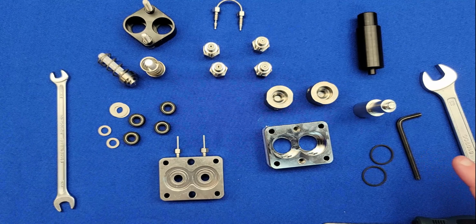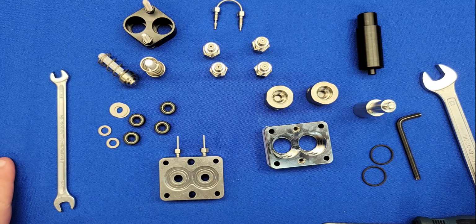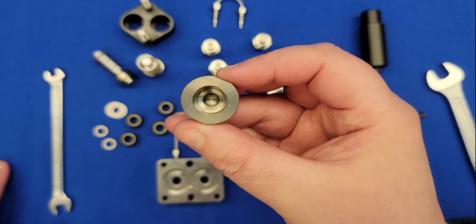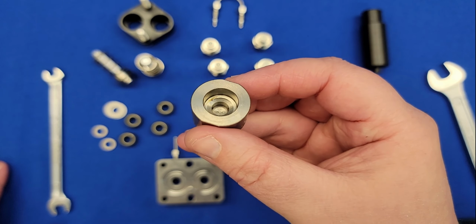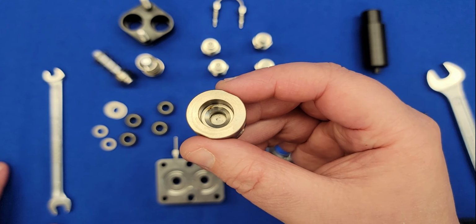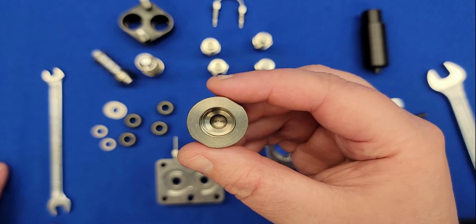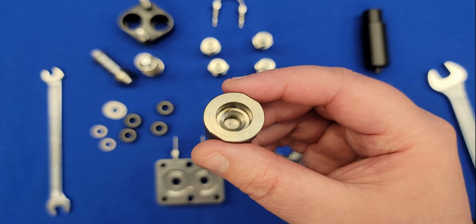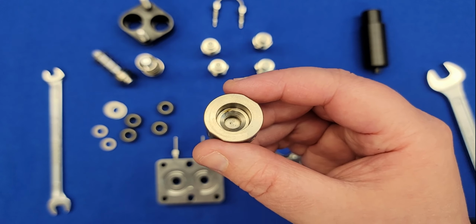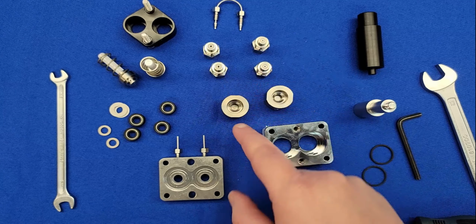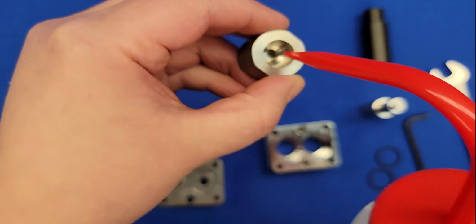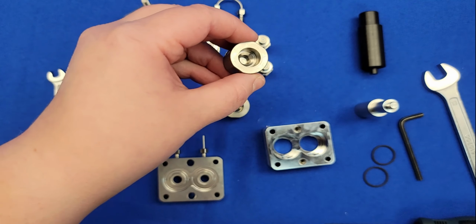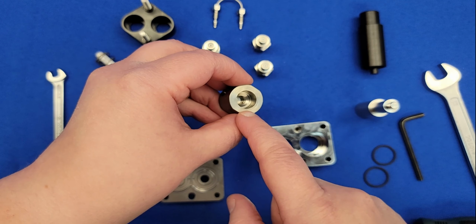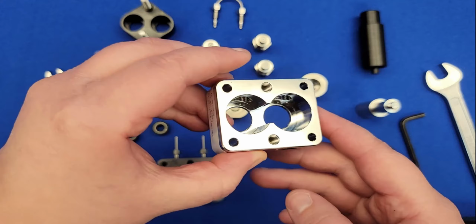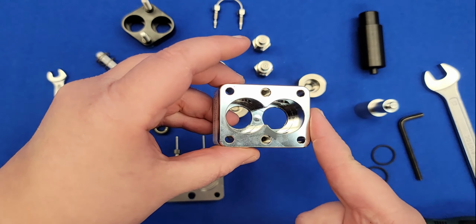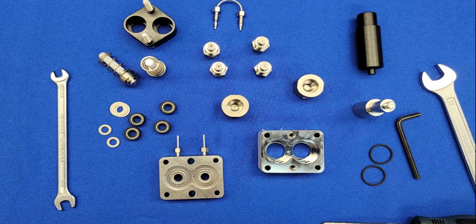So at this stage, that's where you want to clean up. So in the insert right here, right now you can see that there's a little bit of particles. Sometimes you're going to see particles from your seals, you're going to see some buildup from your mobile phase, so you want to clean this up. So you take some solvent, spray it in, use some Kimwipe and just wipe the entire thing inside. Make sure that this is also clean, and if it is, then you're good to start back up.